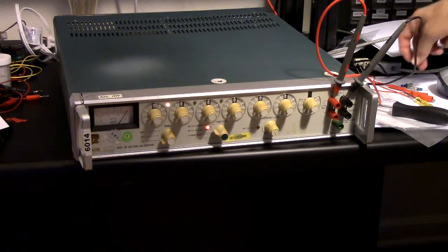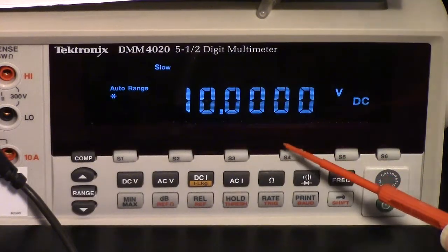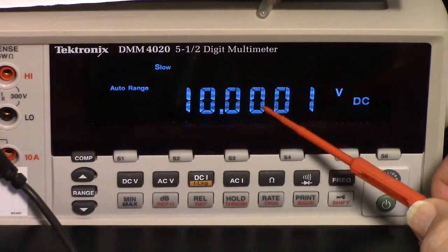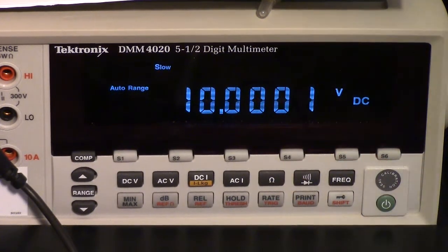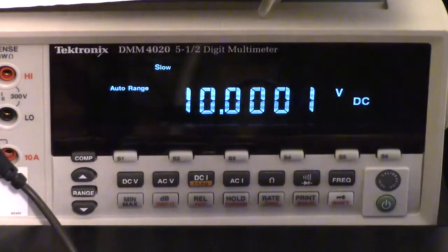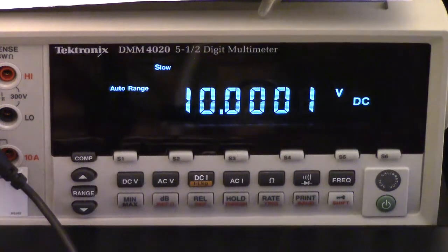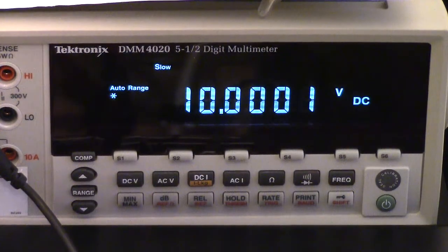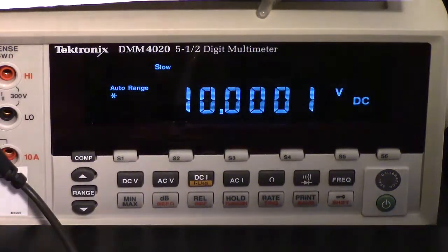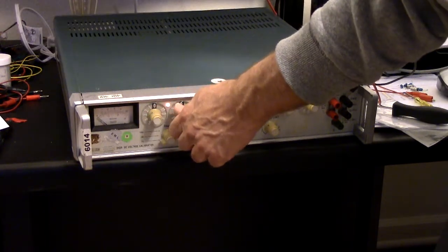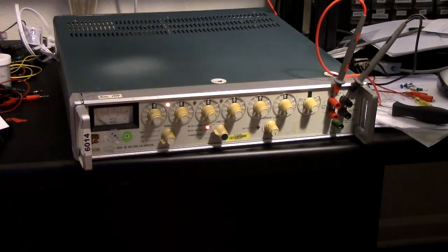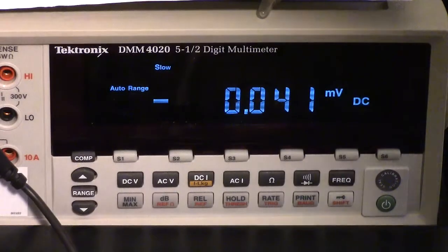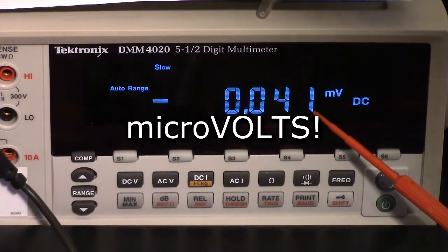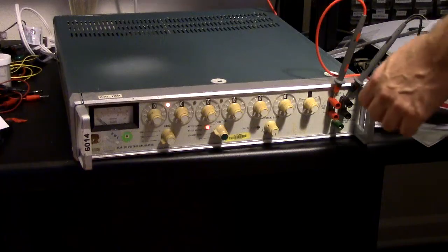And on the Tektronix, we've got 10.0001, which is, you know, off by one count. It's well within spec for this thing, or the combined thing is well within spec. The place where it may not be in spec, if I go down to, well, again, zero, I think it wants to see something like 20 microamps. And we're seeing about 40. Okay, minus 40.